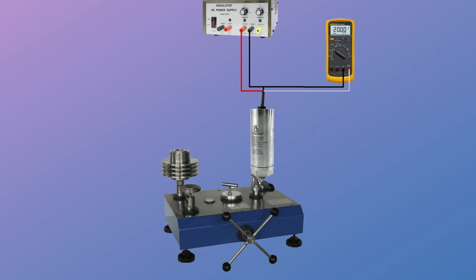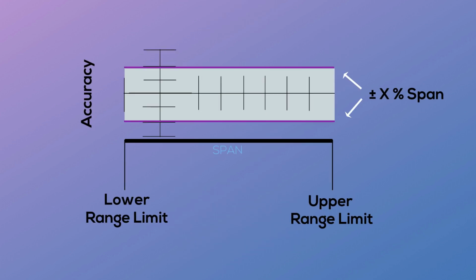Once the zero reading is recorded, pressure is then applied to the full scale range of the transmitter. Once full pressure is reached, verification of the full scale reading can be determined. In this example, that would be 20 milliamps at 500 psi. There will be a factory tolerance on this full scale reading and can be obtained from the product data sheet or the factory direct.